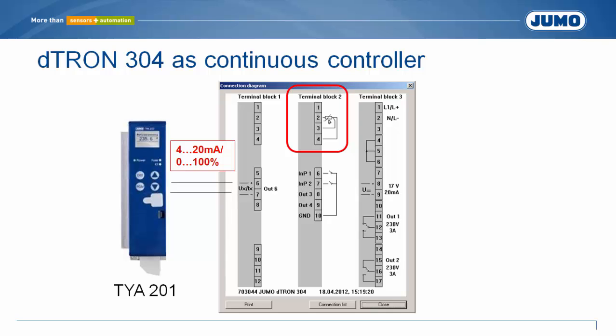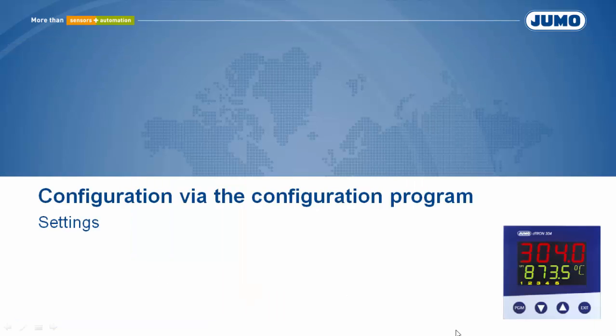Using the configuration program, the controller should be configured for the following application. In an annealing furnace, temperature measurement is done with a RTD temperature probe in 3-wire circuit. The heating of the plant is effected electrically by a power controller. Operating the power controller is done with a 4 to 20 milliamp signal. Proportional to this signal, the power controller gives electrical power into the heater. A new file is created.